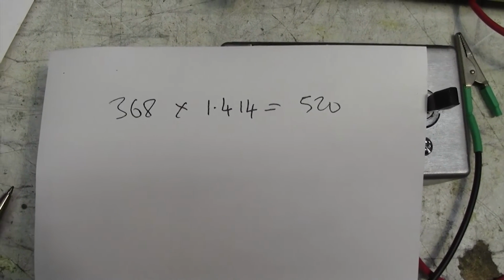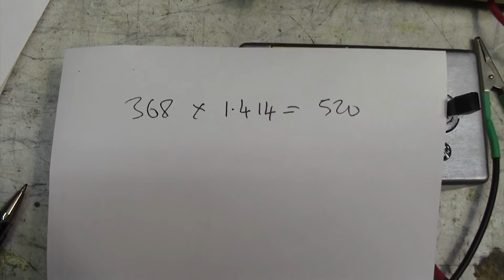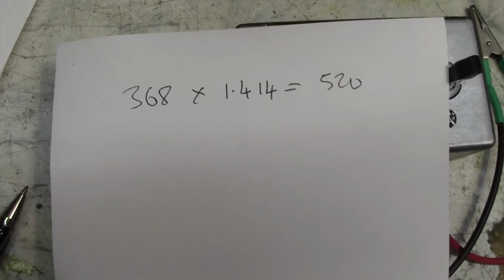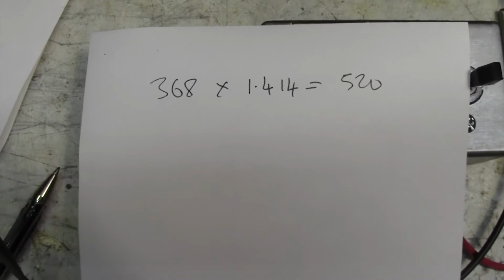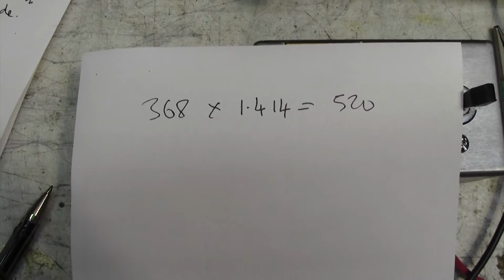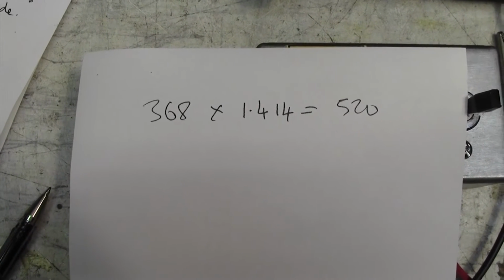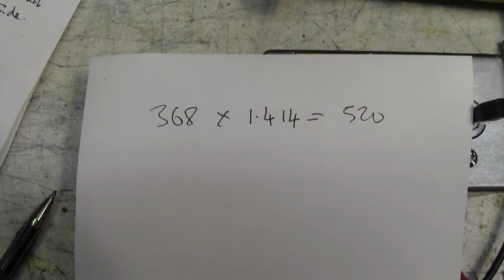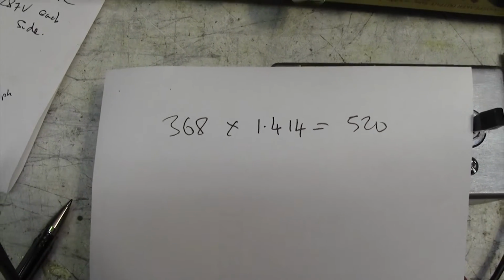So in theory, we could rectify that and get 520 volts DC from that transformer. In practice, by the time you've lost a little bit and current starts to be drawn, you'll get 470, 480, 490, which is exactly the kind of voltage we would be expecting.